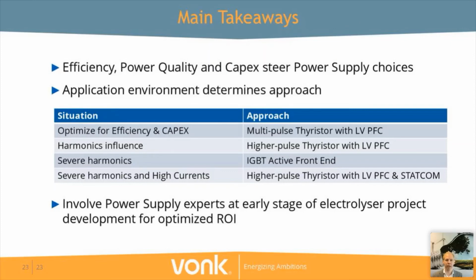The first one is a situation with less harmonic influence, where you want to optimize for efficiency and capex. As I mentioned, this is the lean and mean approach. What we would suggest is to apply a multi-pulse thyristor topology in combination with power factor compensation at low voltage level. If you have a situation with more harmonics influence, we would suggest to use a higher pulse thyristor topology, again with low voltage power factor compensation.